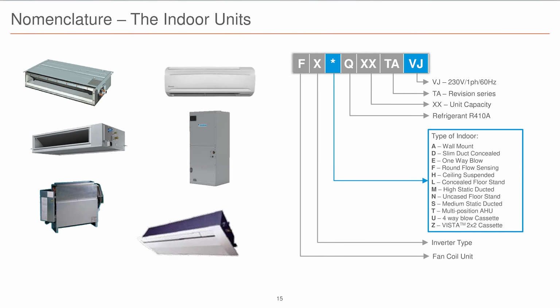Nomenclature, right? I don't expect you guys to know this. Just go in this actual manual itself and you'll be able to read what the model numbers are. The biggest one that I'm going to point out that you need to know is capacity. You need to know exactly what capacity that unit has, and you can tell that by the two numbers in the model number. So if it's an FXMQ, the M stands for high static, and the Q is because it's R410A, which might change shortly in the next couple of years.